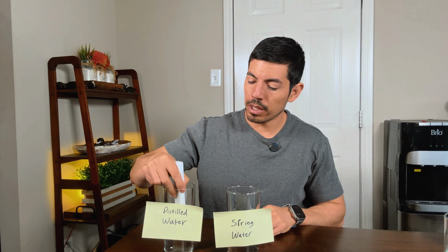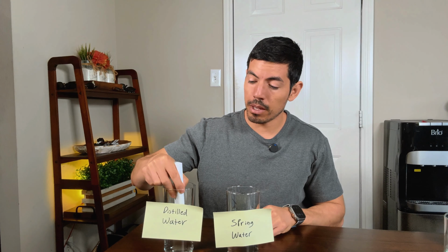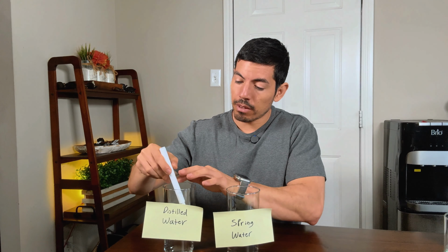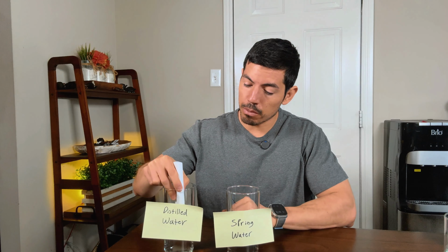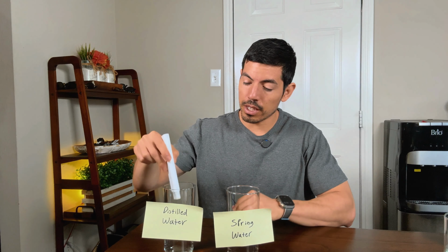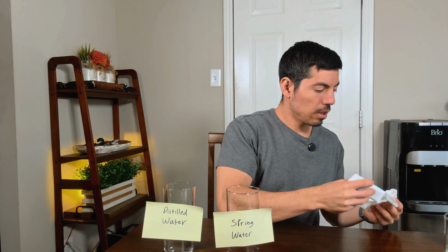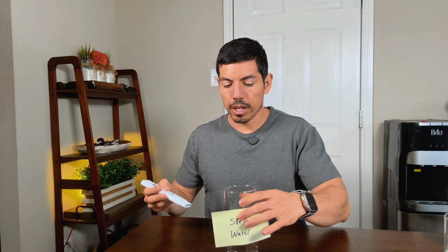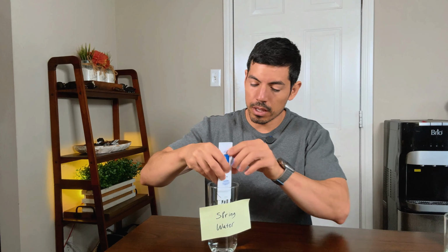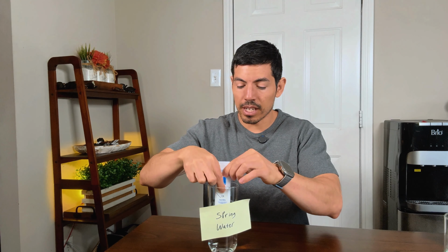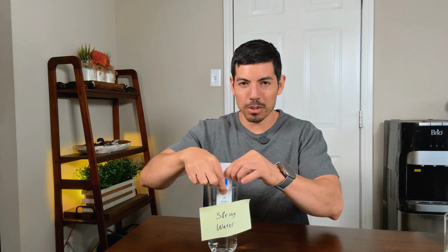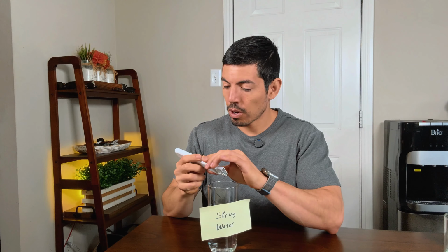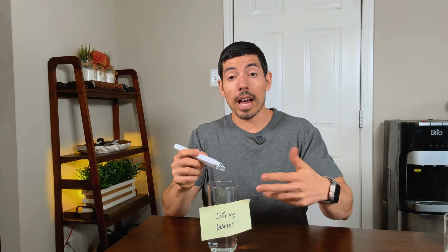Go ahead and hold down for 5 seconds on the M. Okay, then press the down arrow and power button, and press the M once more. Calibration succeeded. Then we'll go ahead and test the spring water again. Get that reading. So I love how instant it is. You don't have to sit here for like 2 minutes just holding this. It really just instantly reads it out. Okay, so for the spring water, we have a COD of 0.2, TOC of 0.2, TDS of 43. Definitely higher because it has minerals in it. And then excellent, 98 score.